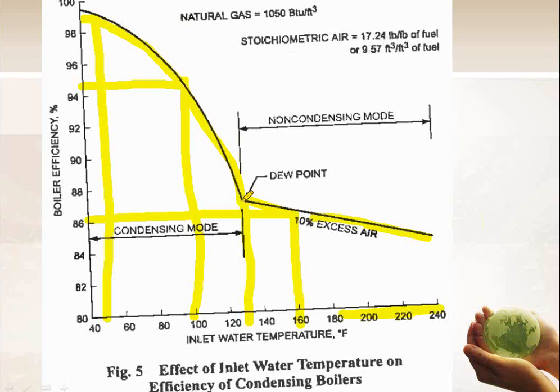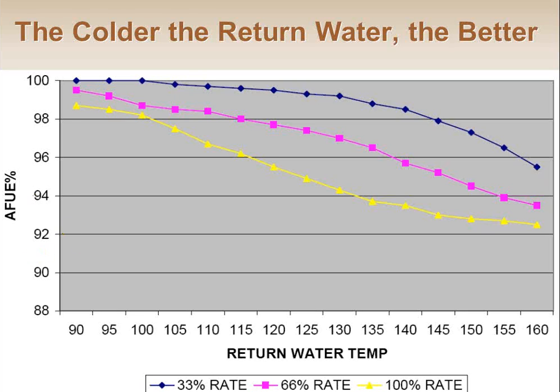And that cold return water hitting those cooler flue gases towards the back end of the heat exchanger, they're going to condense. And it takes a lot of energy to change the state of something. So to change something to condense, it takes a lot of energy. So that energy is going to come out of our flue gases, which saves the energy in the building instead of sending it up the stack, right? So the colder the return water, the better for a condensing boiler.